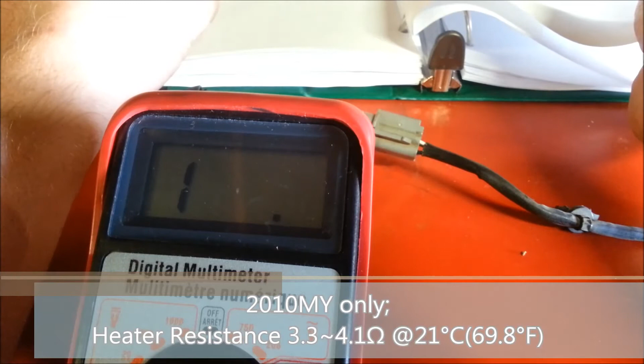To make sure the heater is working, we measure the resistance between terminals 3 and 4, and check that it's within specification. The resistance we're looking for is 3.3 to 4.1 ohms at 21 degrees Celsius.